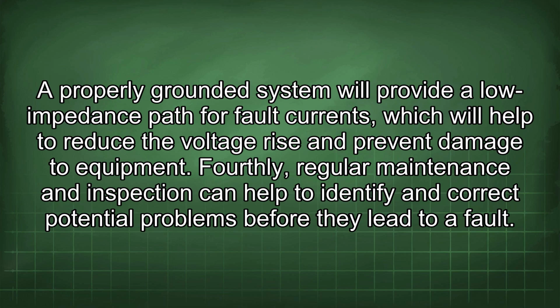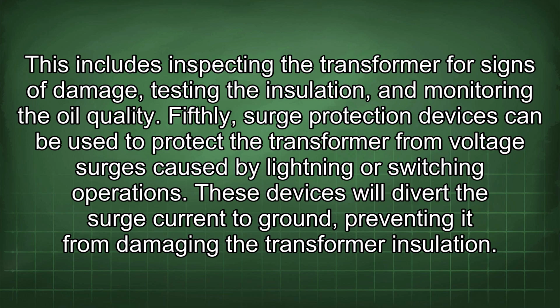Fourthly, regular maintenance and inspection can help to identify and correct potential problems before they lead to a fault. This includes inspecting the transformer for signs of damage, testing the insulation, and monitoring the oil quality. Fifthly, surge protection devices can be used to protect the transformer from voltage surges caused by lightning or switching operations. These devices will divert the surge current to ground, preventing it from damaging the transformer insulation.